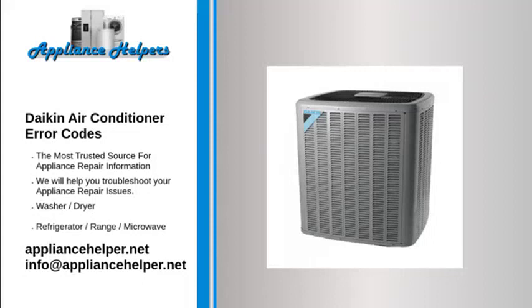Code C9. Problem: malfunction of suction air thermistor. Defect of connector contact. Defect of thermistor for suction air. Code CA. Problem: malfunction of discharge air thermistor. Defect of connector contact. Defect of thermistor for discharge air. Code CC. Problem: malfunction of humidity sensor system. Defect of connector contact.